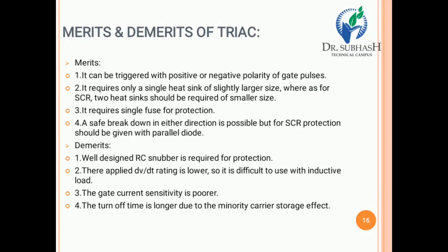It requires only a single heat sink of slightly larger size, whereas for SCRs, two heat sinks of smaller size are required. It requires a single fuse for protection. That is the major advantage. A safe breakdown in either direction is possible, but the SCR protection should be given with a parallel diode, right?